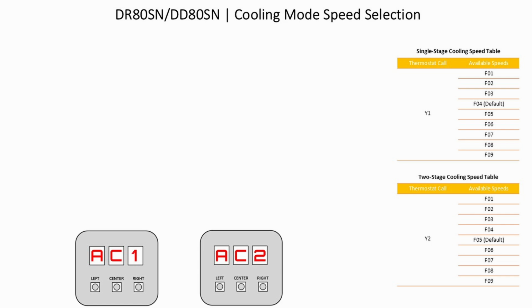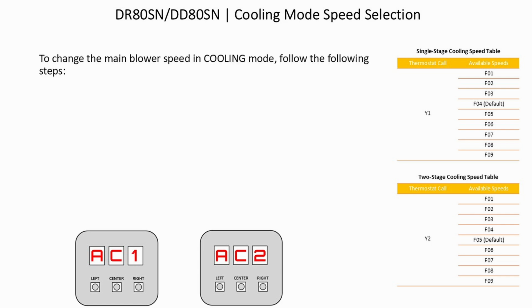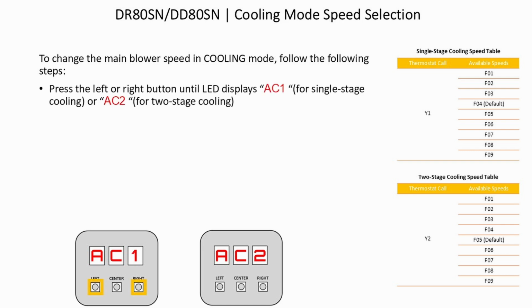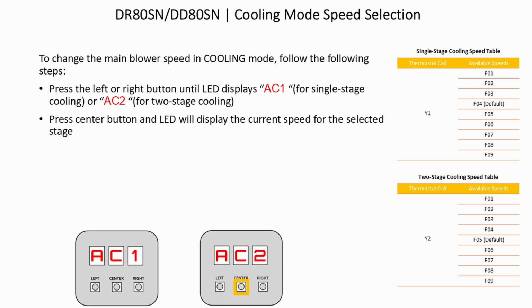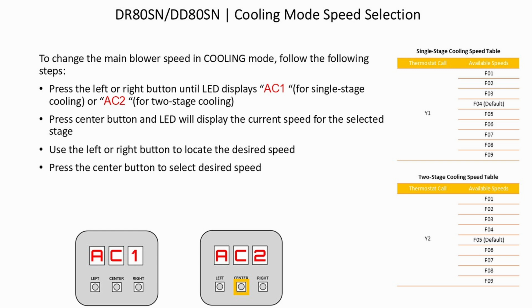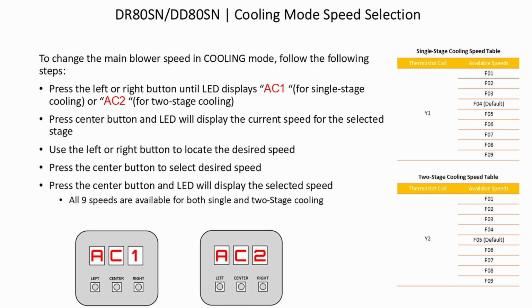Cooling mode speed selection. To change the main blower speed in cooling mode, follow these steps. Press the left or right button until the LED displays AC1 for single-stage cooling or AC2 for two-stage cooling. Press the center button and the LED will display the current speed for the selected stage. Use the left or right button to locate the desired speed. Press the center button to select the desired speed. Press the center button again and the LED will display the selected speed. All 9 speeds are available for both single and two-stage cooling. The chart on the right shows F04 is default for single-stage cooling, F05 is default for two-stage cooling.